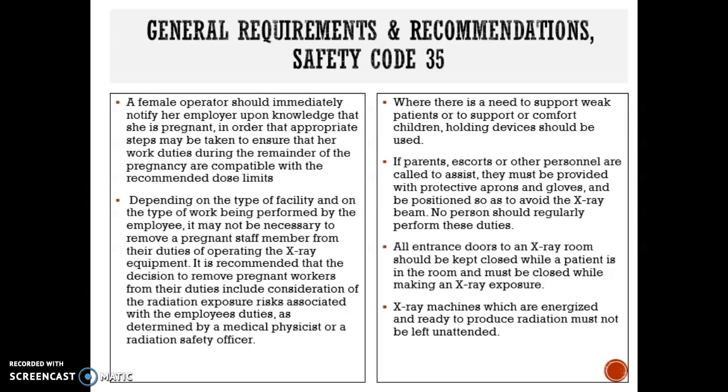All entrance doors to the X-ray room should always be kept closed while the patient is in the room. You don't want any scatter radiation leaking outside the room and affecting anybody walking by. X-ray machines, which are energized and ready to produce radiation, must not be left unattended. You don't want someone walking in and pressing a button and accidentally exposing someone.